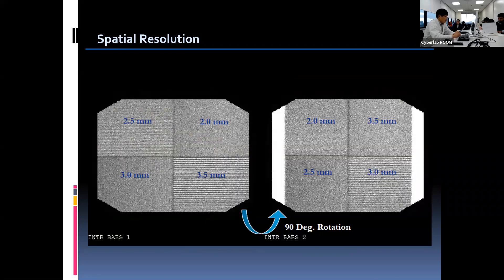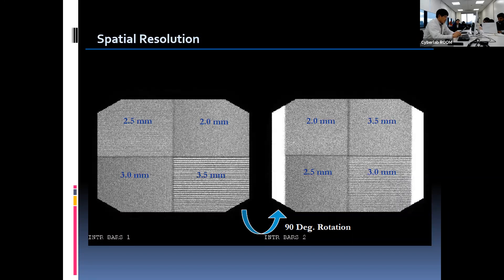This is the result image. The visible smallest bar and space widths should match the allowable limit specified by the manufacturer. The smallest width bar is normally not clearly distinguishable even when the camera functions well. We should be able to discriminate at least the two largest width bars. In that sense, these images show satisfactory spatial resolution.